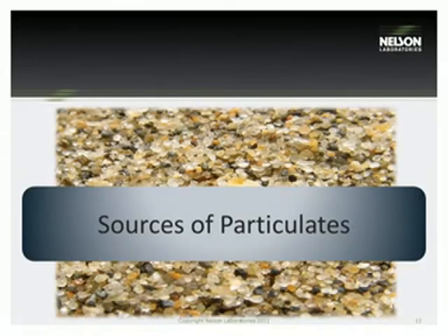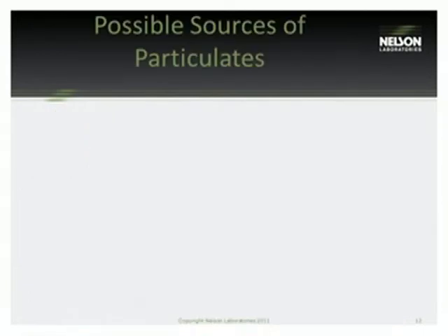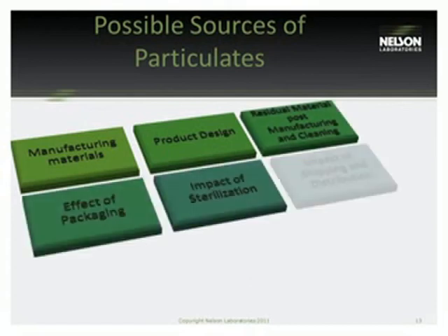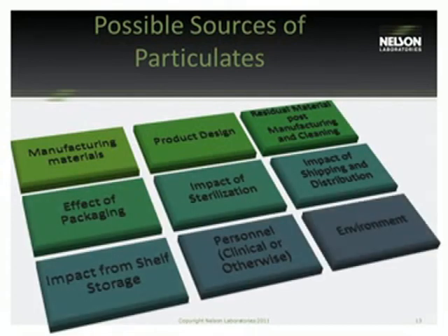The common sources of particulates are often thought of as the manufacturing of devices. Obviously, there's drilling, molding, grinding, and other manufacturing steps that take place during a device's production, and most particulates we find are generated during the manufacturing process during some of the investigations that we participated in. However, there are many other sources of particulate matter. Of these 9 that are listed here, some of the largest contributors we've seen are packaging, as well as shipping and distribution there on the right. Those 2 tend to be a large contributor. Shelf storage and sterilization can also contribute.